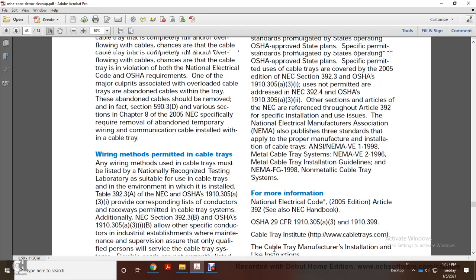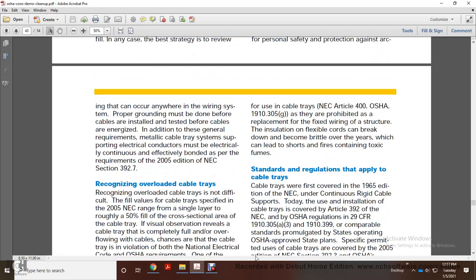Flexible cords are not currently listed for use with the cable tray. Under National Electrical Code Article 400 and OSHA 1910.305(g), they are prohibited as a replacement for fixed wiring over the structure of the installation. Flexible cords can break down and become brittle over the years, which can lead to shorts and fires containing toxic fumes.